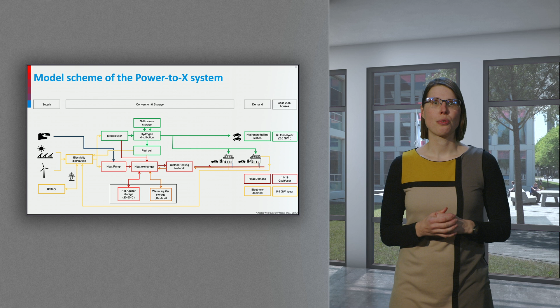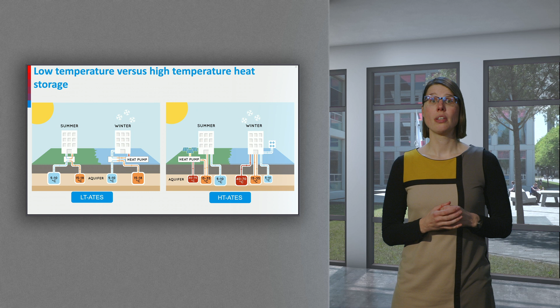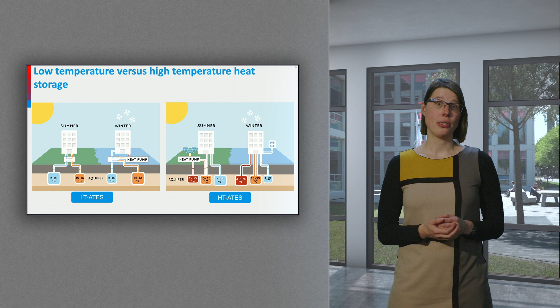In a low temperature ATES system, heat is delivered between 15 and 18 degrees to a building, which means you will always need a heat pump to increase the temperature to the desired level. With a high temperature ATES system, it works the other way around. The heat pump is used in summer here to produce heat at a higher temperature, which is stored in the subsurface. In the winter period, this heat can be used directly by buildings without the need for a heat pump.